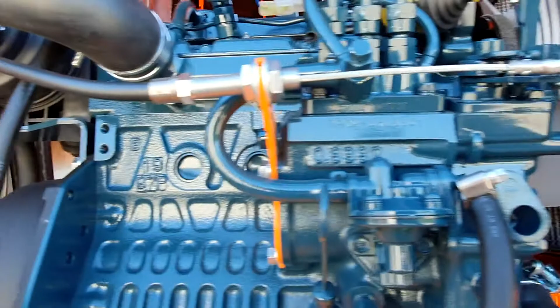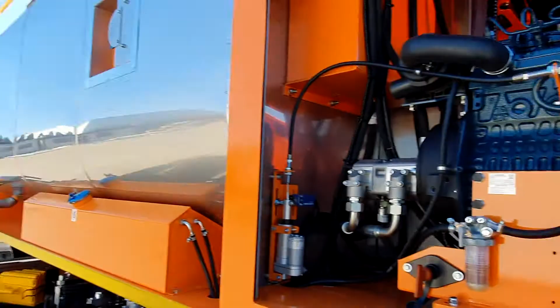This electro servo motor is responsible for controlling the engine speed of this Kubota D902 engine. By means of a joystick from the operator cabin, we control the speed of the engine, but if the engine speed has not reached the set amount, which is described by the position of this sensor, we may not be able to start some modes of circulation. So if the engine speed is too low, not sufficient in our opinion, the sensor will not give the signal, and on the screen, on the PLC touch screen, we will see a red warning that will not allow us to enter the modes of different valve setup for circulation, for small circulation, for circulation through the spray bar.